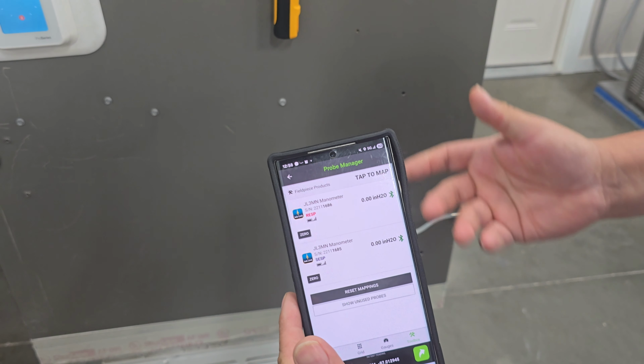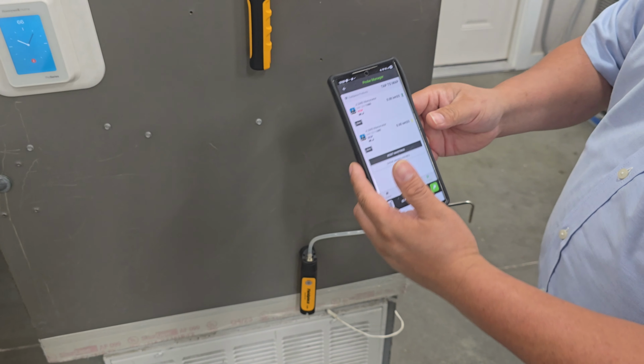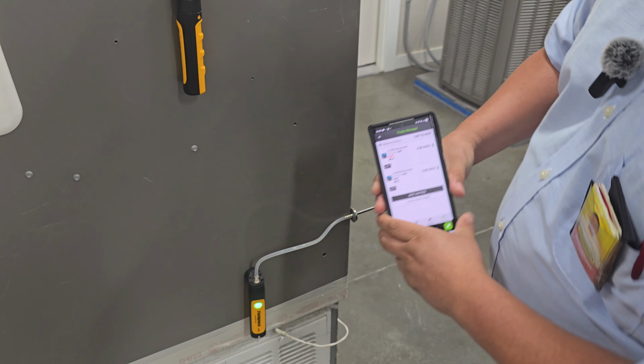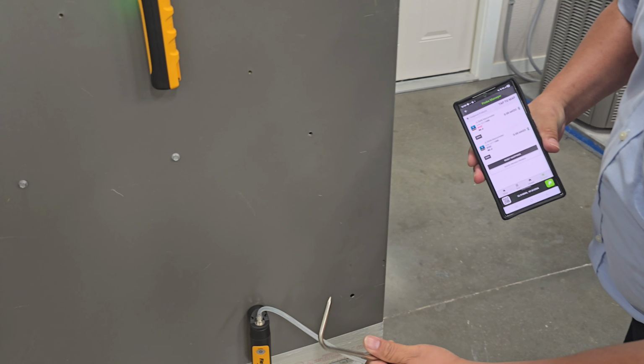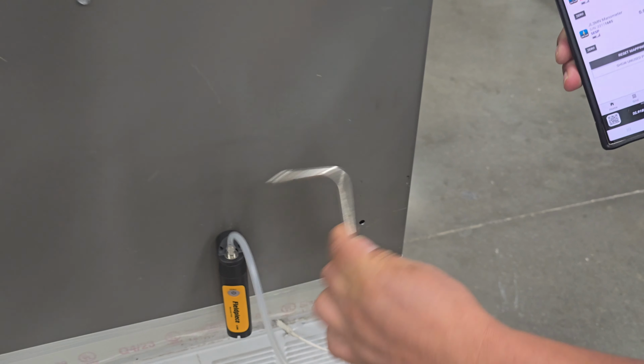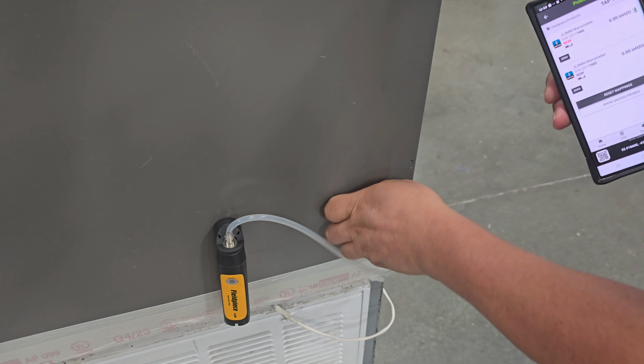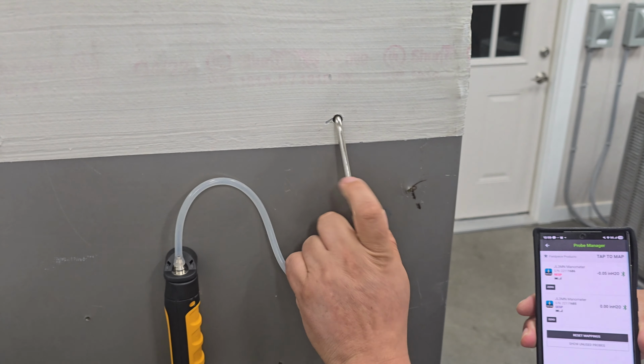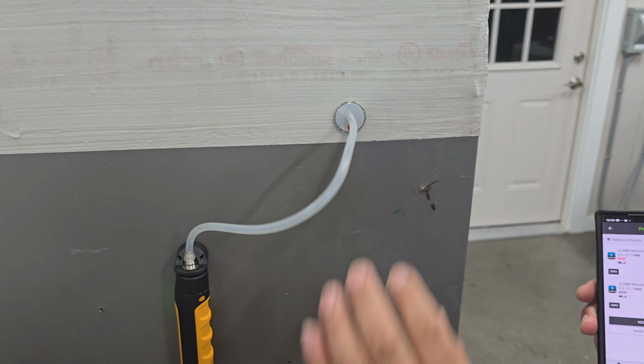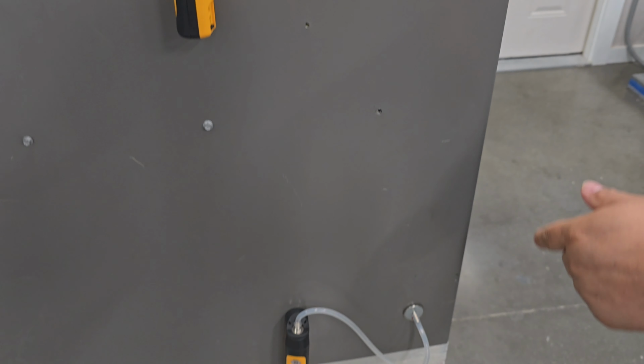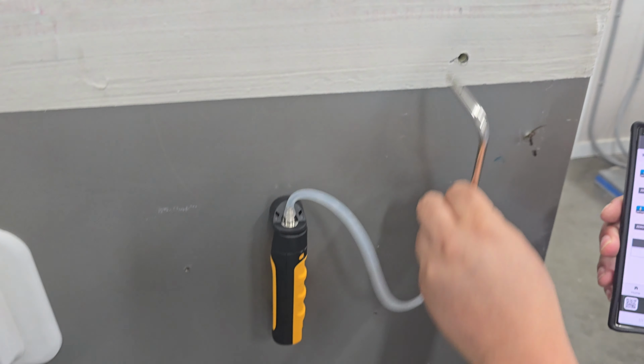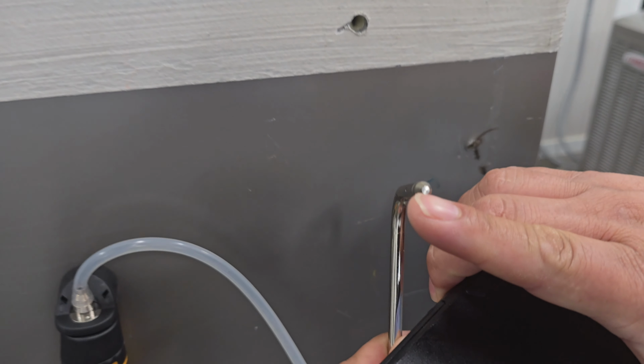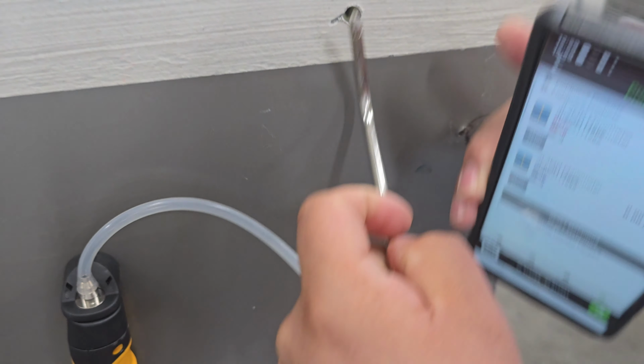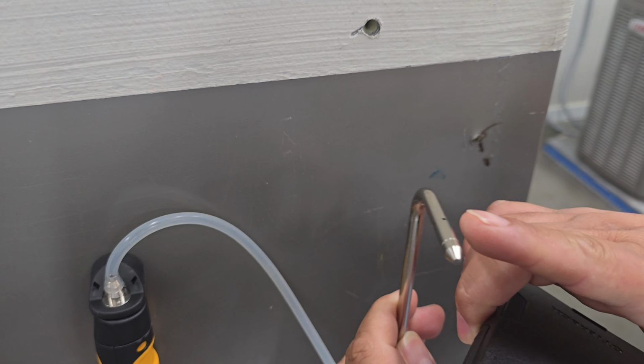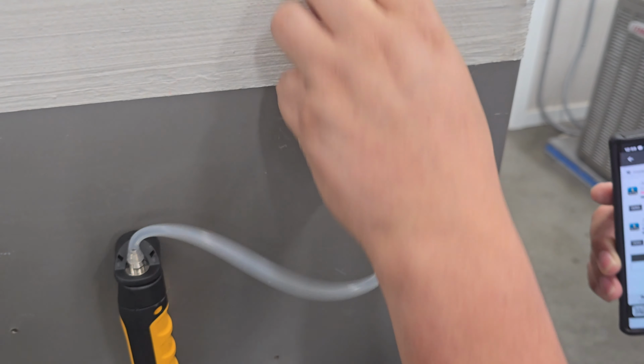Now, I use Measure Quick. This is the one that I recommend. So once you've zeroed it out, we're going to go ahead and insert it. And you'll see an arrow here, and you want to go against the airflow. Same thing with this one. And on these, you can face up or down. If you have a small hole here, you only want to face it with the flow of airflow. But if you don't, and they're on the sides, then it doesn't matter which way you face it.